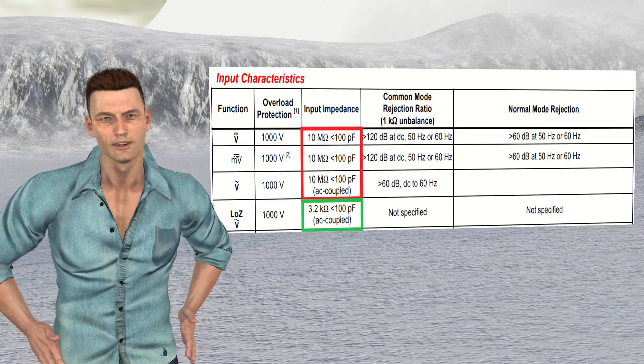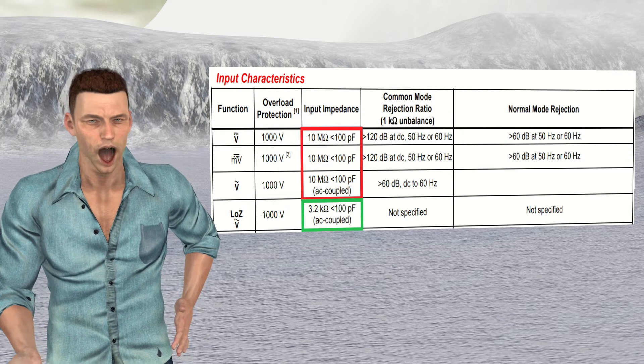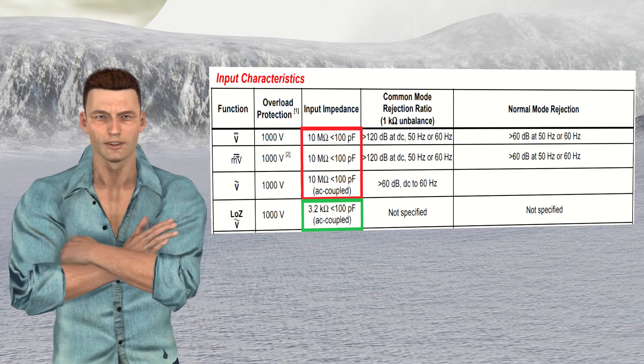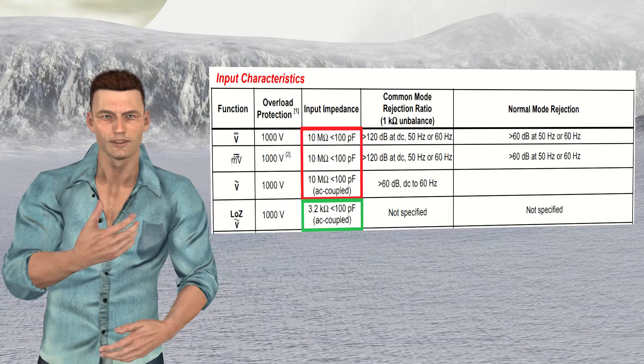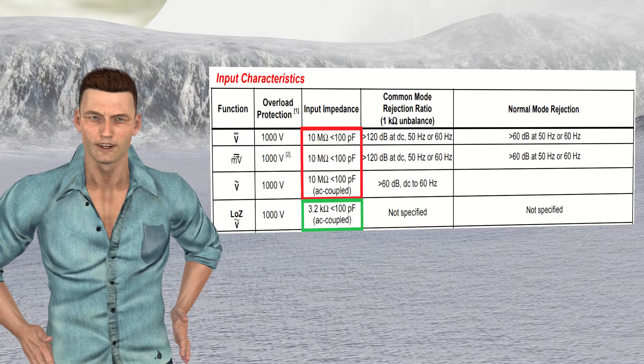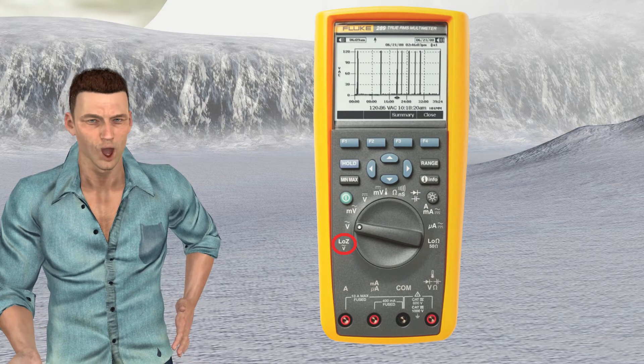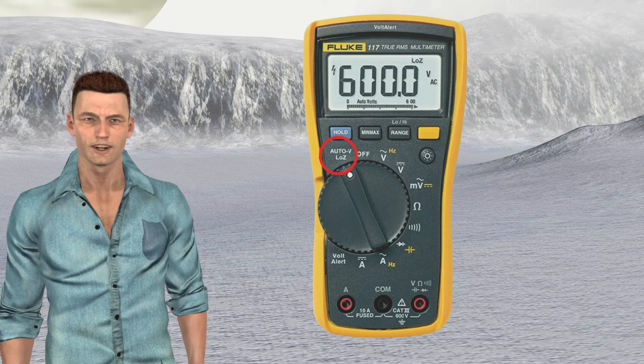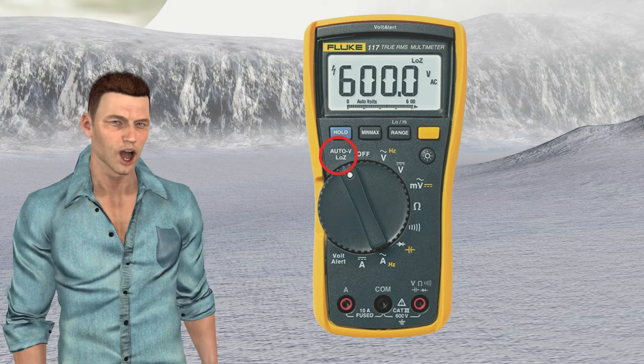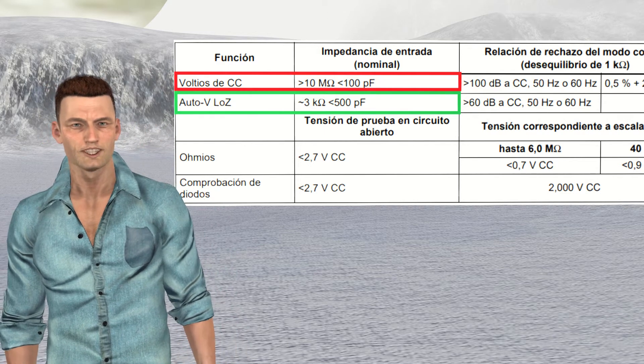When we look at the technical specifications of the Fluke 289 multimeter, we see that two different impedances appear. On the one hand, the typical impedance of 10 mega ohms appears for the measurement of direct and alternating voltages, and on the other hand, an impedance of 3.2 kilo ohms appears for the measurement of alternating voltage associated with a function called LOZ. This name LOZ comes from low zeta, that is, low impedance. The Fluke 289's rotary knob allows selection of this LOZ function, and the Fluke 114, 116 and 117 multimeters also have that LOZ function with an input impedance of about 3 kilo ohms in that mode.